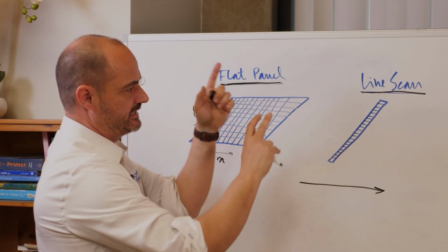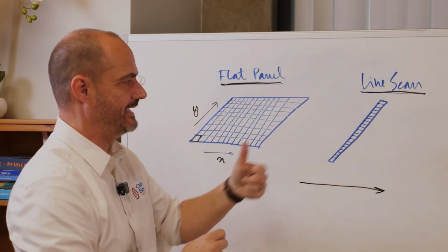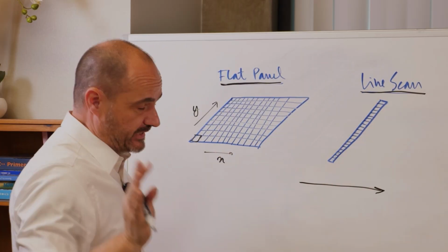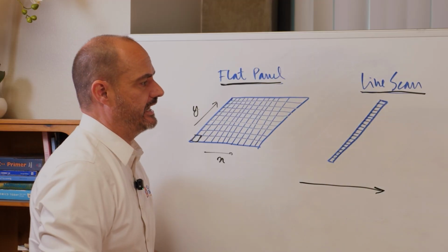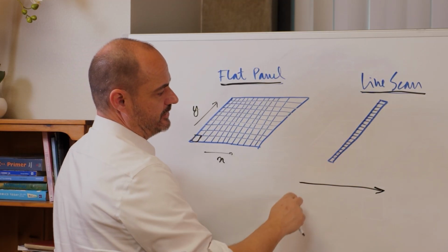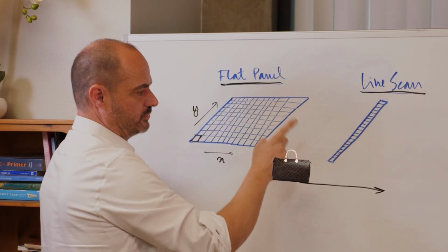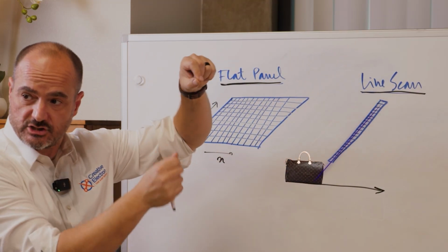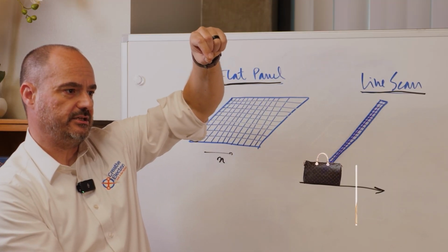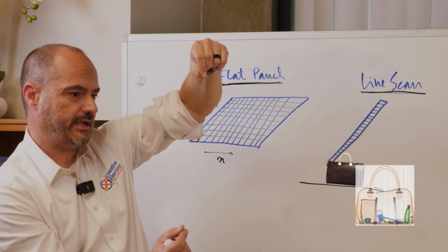in a very specific speed, right? All this plays into it. We're going to have another video talking about the details, how the line scan works and how TDIs work, what's the difference between a standard line scanner and a TDI. But that's the next video. We're going to add that to our X-ray University. But a simple line scanner works by reading this line multiple times. Every time you read a line, it's basically one strip of your X-ray sample, and then you move the object a little bit and take another snapshot and read it. You go on reading those strips of your sample, and by combining them together, you build a nice X-ray image of your sample.